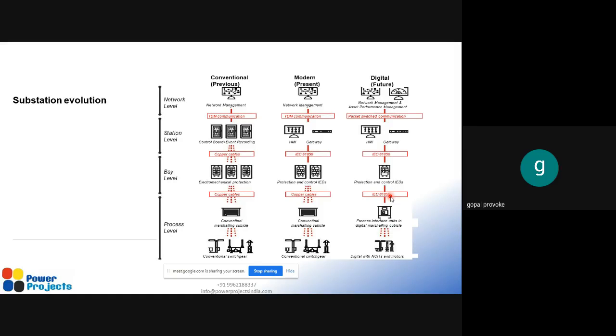For SCADA applications, similar to present day applications, we use 61850. In present day applications, we use 61850 only for SCADA applications, from relay to SCADA, but not for CT to relay. So there are two interfaces: CT/PT to the relay, and relay to the SCADA.